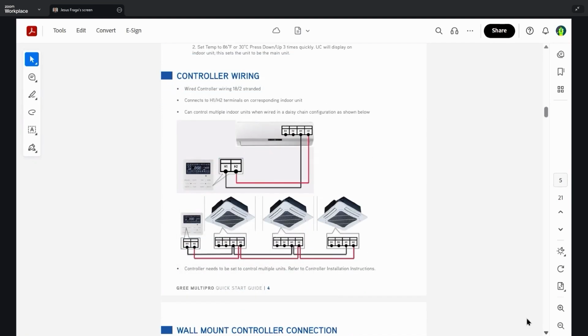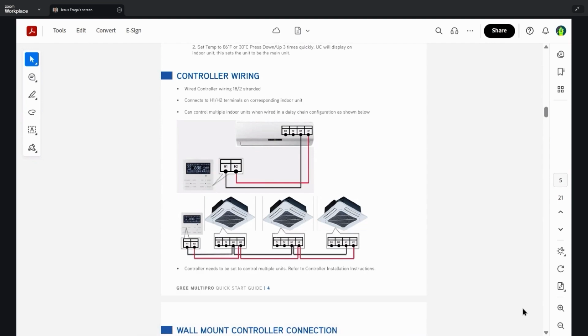Moving on now to the control wiring. Our ductless systems come with a remote controller, but they do have the option for a wired controller to be connected to the system. This is via H1 and H2. For example, here we have a wall-mounted unit. We have D1 and D2, which is coming from an outdoor condenser. And we also have another set of pins here, H1 and H2, which is our wired controller. So we open up this case and we'll see this terminal block there next to the line voltage terminal block.